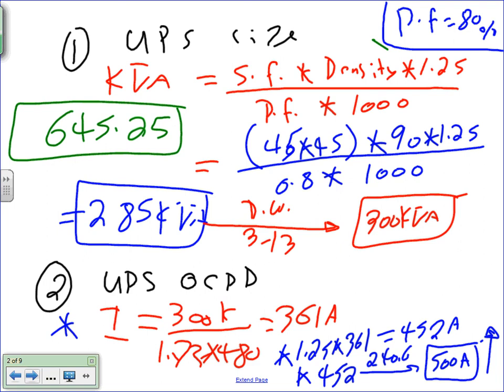Yes, sir. On the size of the UPS, we did the continuous 1.25. Really, that first one was mostly for opinion. Again, let me just say, it's for losses, to accommodate for the losses in the system, because you're converting AC to DC and all this stuff. So we're upping it 25% to cover our butts, basically. The rest is continuous. That's where I get my continuous on the overcurrent protection device. Okay, so that's my answer. Any questions, guys?